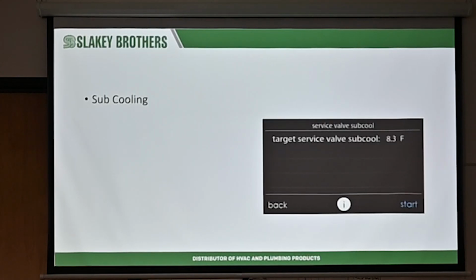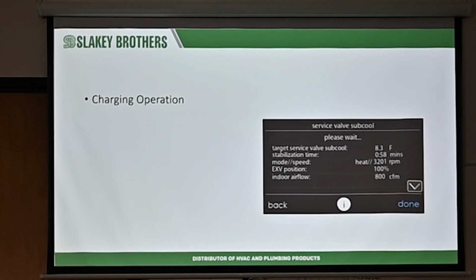Same thing as well, if you're going to do subcooling, it's going to tell you what your subcooling should be. Depending on your unit, like the Evolution Extreme does do subcooling, or let's say the older versions of the 5-stage or the older Evolution, you need to know you have 8.3 degrees subcool. Now you can go outside, hook up your gauges, charge it to 8, make sure you're at 8.3 degrees or around there, and then you're good to go. As you can see, in this mode, it's just doing it all on its own.